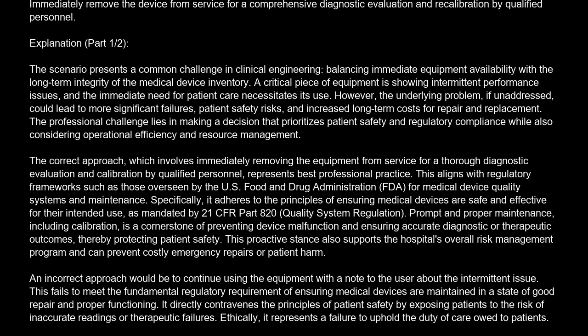Prompt and proper maintenance, including calibration, is a cornerstone of preventing device malfunction and ensuring accurate diagnostic or therapeutic outcomes, thereby protecting patient safety. This proactive stance also supports the hospital's overall risk management program and can prevent costly emergency repairs or patient harm. An incorrect approach would be to continue using the equipment with a note to the user about the intermittent issue. This fails to meet the fundamental regulatory requirement of ensuring medical devices are maintained in a state of good repair and proper functioning.